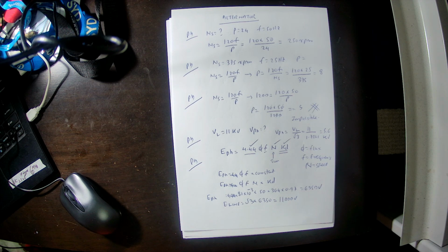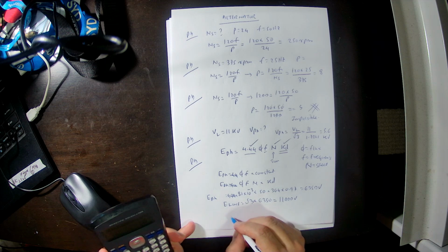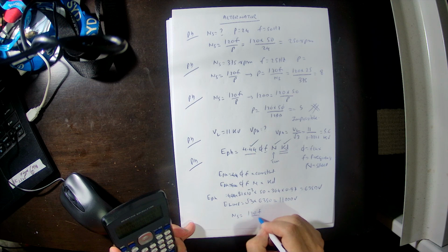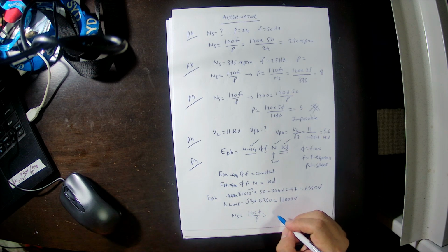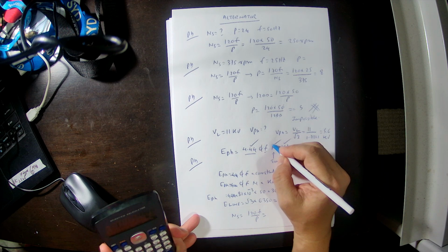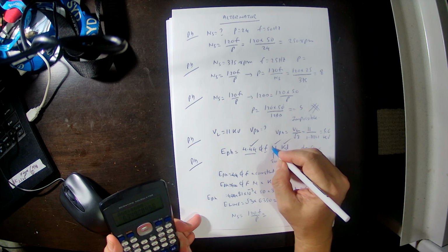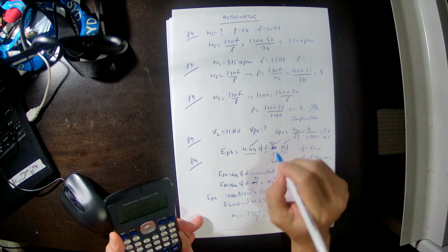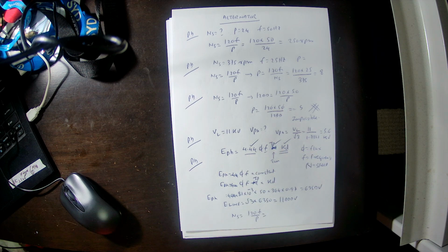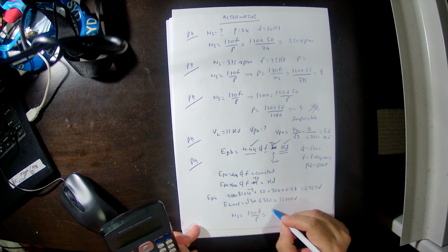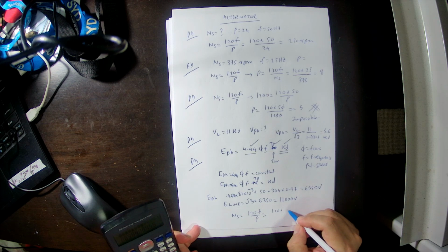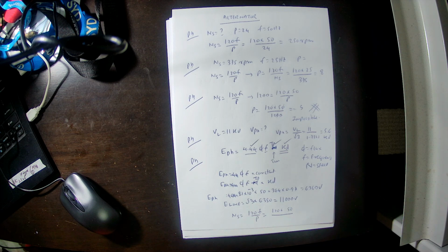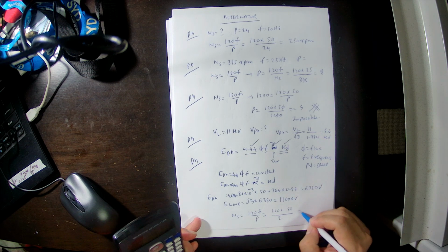And also we can calculate speed, N equals 120 F divided by P. Here the 120 times frequency 50, divided by the number of poles. With 2 poles, that will be 3000 RPM.